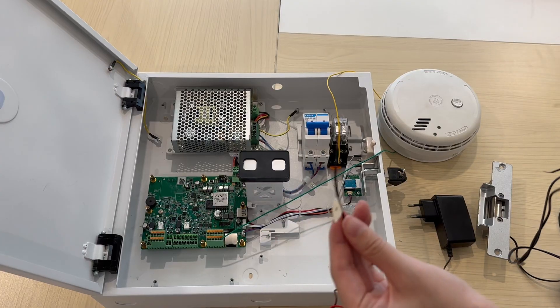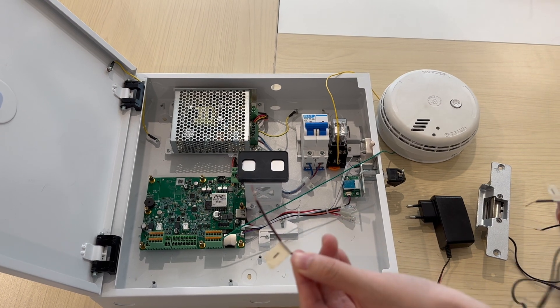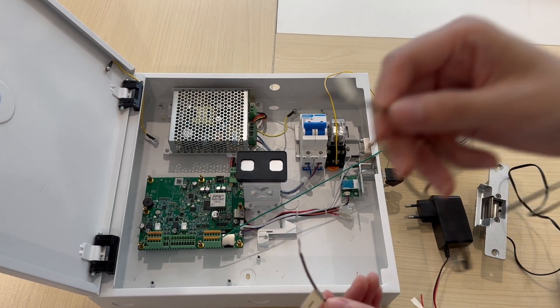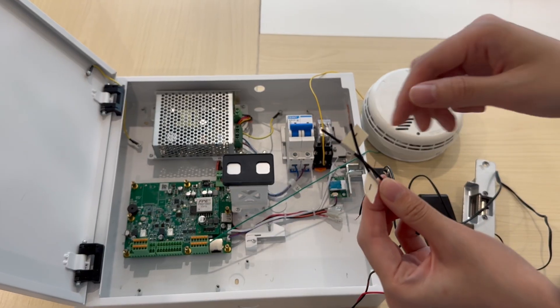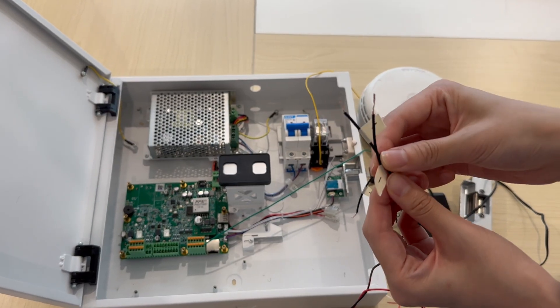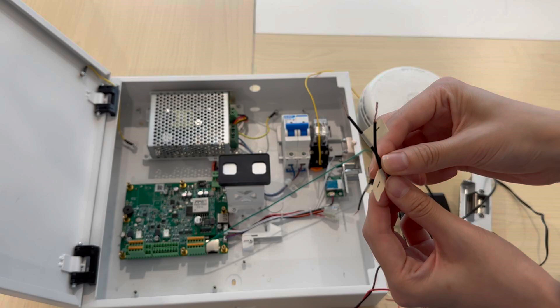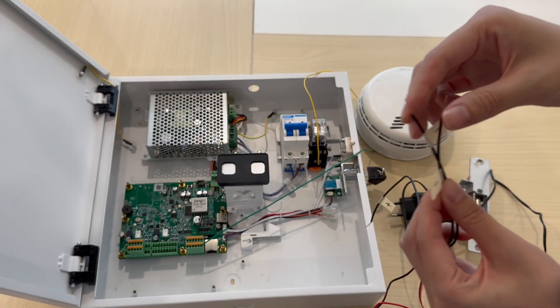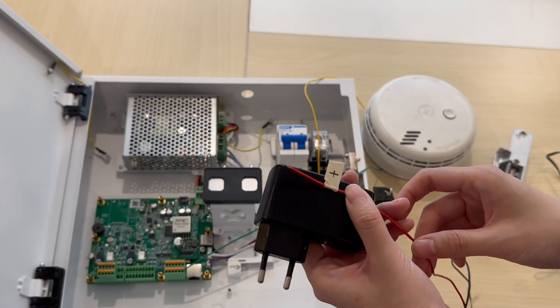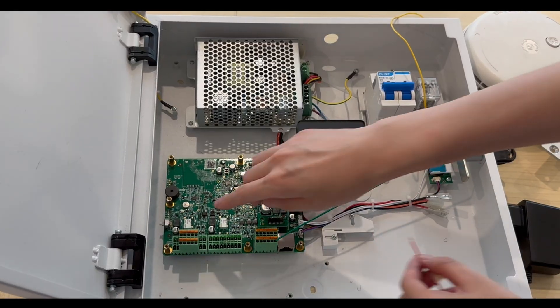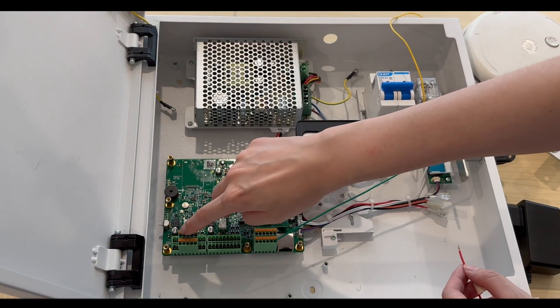Then we'll connect the lock that will be triggered by the activated fire alarm. We use a fail-safe electric strike. Connect the negative wires of the lock and power supplier together. Choose any of the relay terminals. Here we take Relay B.